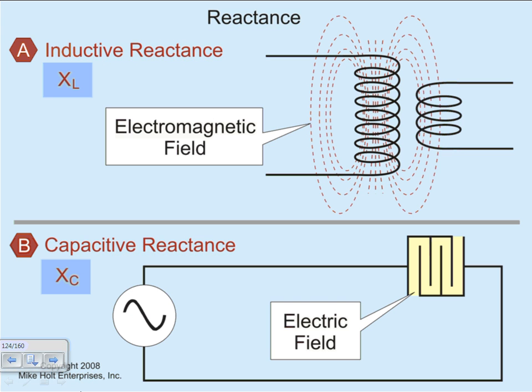How do you take 100 amps from Excel and use 100 amps? And by the way, you're only paying for 70 amps when you use the 70 amps. So Excel is upset at you because they're giving you 100 amps, and you're only using and paying for 70 amps out of it. Why are you using 70 amps? Because your power factor in your building is bad. Why is it bad? Because you have a lot of motors that have XLs in them that are screwing up the phase shift between the voltage and the current. See where everything is tied together to the XL?